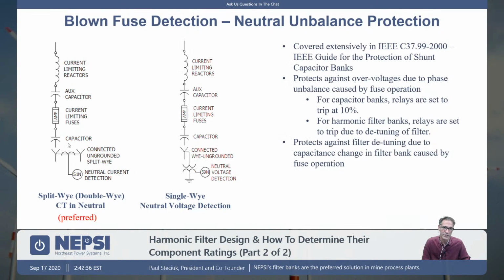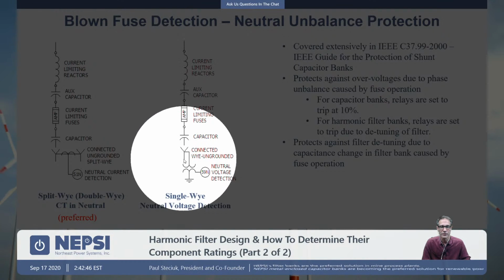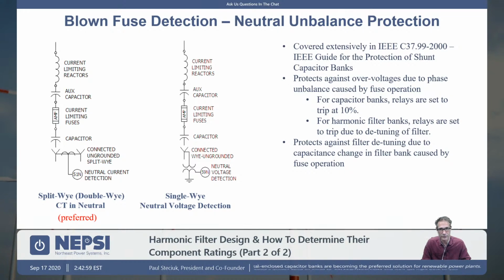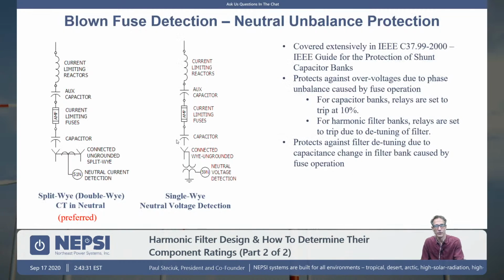Okay. The other reason is that the switching device, and we don't show a switching device here, but typically up here there's a breaker or some type of switching device, will see a higher recovery voltage with this type of arrangement. When this switch up here opens, you have trapped DC charge on the capacitor down here. That trapped DC charge will want to discharge through the transformer here. Remember the transformer has high impedance for 60 hertz or 50 hertz, but to DC, that trapped charge is a short circuit, and you get a spike, just like you would in the coil of a car. That spike can cause restrike within the capacitor bank and the switching device, and that restrike can result in capacitor failure. So you inadvertently put more duty on the switching device when you go with a neutral PT to detect blown fuse conditions.